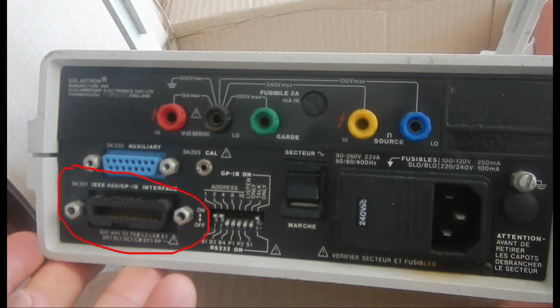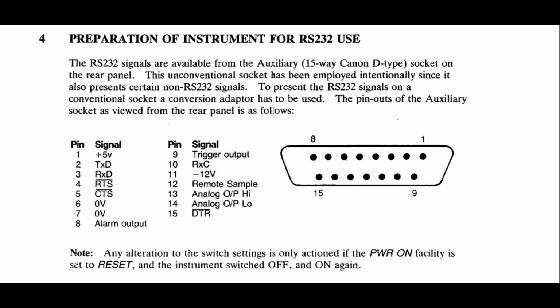This instrument has the IEEE 488 interface that was the most common interfacing option in those years. But it can also be interfaced via the RS-232 serial interface, which was a less common option on those test instruments.